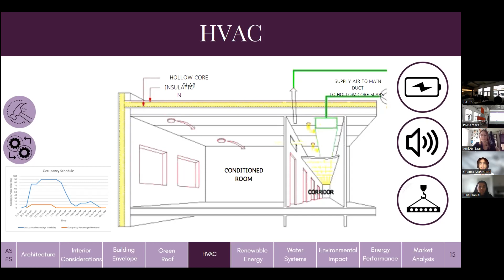Our considerations while developing this were the soil composition, depth to bedrock, density of material, depth to water table, and average moisture content. Together, this would constitute an extraction rate of roughly 40 watts per meter squared. Altogether, this will consist of 196 boreholes covering about 22% of the total available area. This configuration is able to supply 100% of peak energy consumption using a depth of 115 meters per borehole.